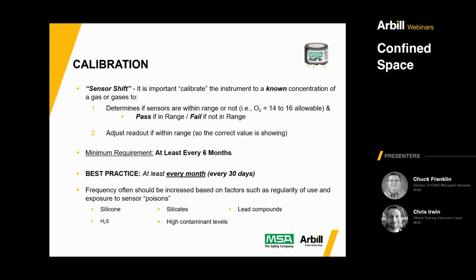Basically, the two things calibration will do are, number one, check whether the sensors are reading within a defined range. We know in the bottle of gas, for example, that we have oxygen at 15%. If it's anywhere between 14 and 16, it'll pass the test. That said, we don't want you getting an incorrect reading. So if it's within an allowable range, the second thing that happens is the detector will automatically adjust its readout so it's correct. Now, if it's outside the allowable range, it'll fail the test and tell you that sensor is bad. That doesn't mean you have to get a new detector. It just means you need a new sensor, like we can see at the top of the screen. It will tell you that right on the screen at the end of the test, and it really won't let you forget that. It'll show you a heart symbol in some cases, letting you know this needs to be replaced.